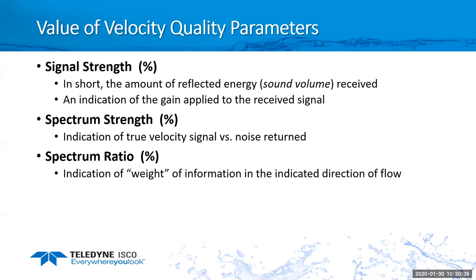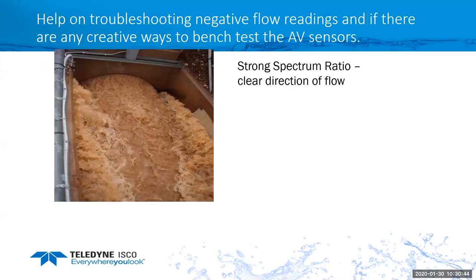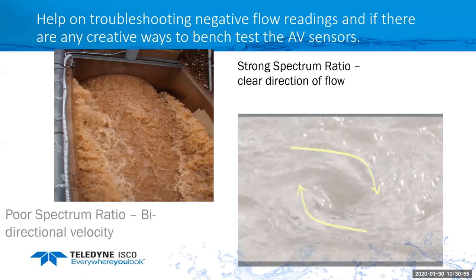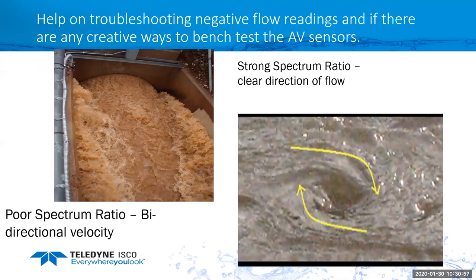And then last, the spectrum ratio tells us the direction of the flow. In this example of the spectrum ratio, you would see all the water is going one direction, you should get 100% ratio, indicating all the water is going one direction. But if you see something like this, where the water is swirling, then you're going to have a lower ratio, which could be down to zero if it's seeing equal positive and negative velocity. This is helpful when you have an application where you're starting to get dropouts on velocity, where it was working fine and then now we get a poor ratio and possibly negative velocities.